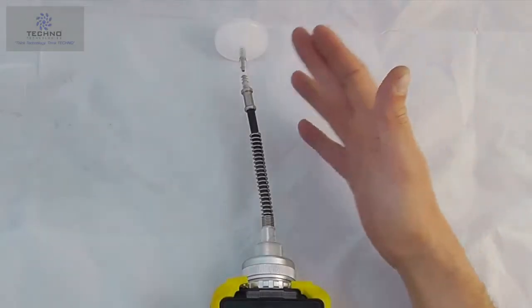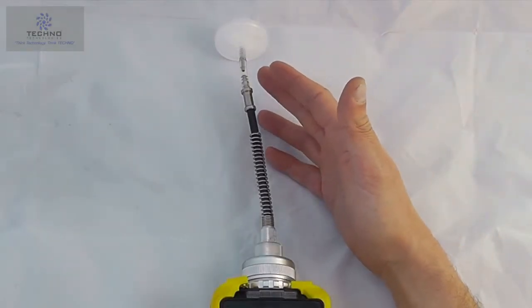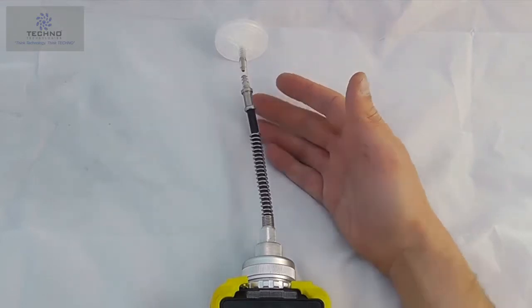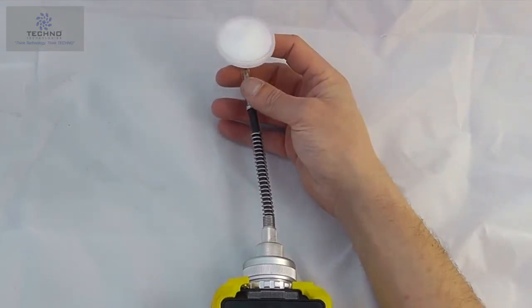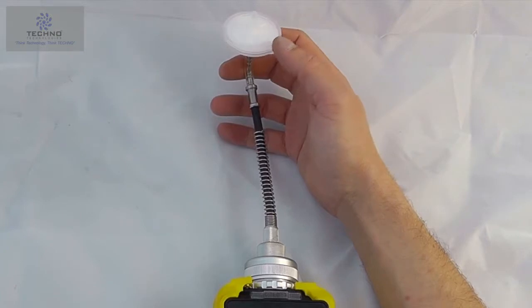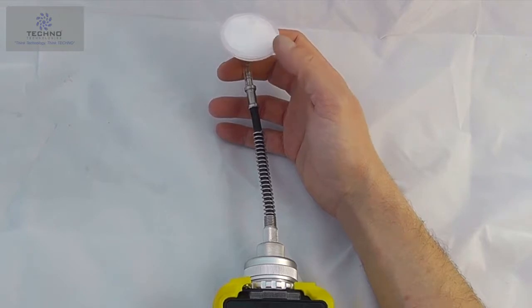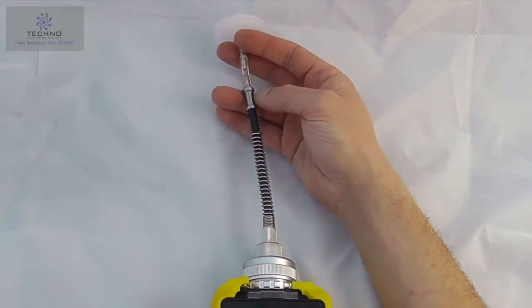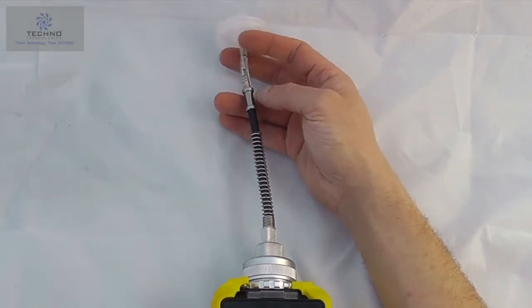The first thing to always look at is the hydrophobic filter on the top of the instrument. Always make sure the instrument is in operation with a hydrophobic filter. Check the filter itself to make sure there's no sign of any contaminants, dust or humidity forming. If there is, take the filter off and replace it with a nice fresh new one.